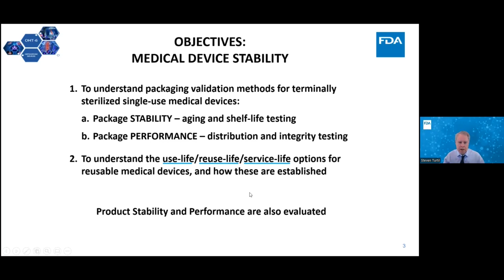So I'm going to introduce you to some terms, but the first and most important one for context is a sterile barrier system, and we often abbreviate this as the SBS. This is the minimum packaging that minimizes the risk of ingress of microorganisms and allows aseptic presentation of the sterile contents at the point of use. And from a microbiological perspective, the sterile barrier system should be designed to assure adequate sterilant penetration. That's going to vary depending upon the sterilant, as well as maintenance of sterility, from the point of sterilization and manufacture to the time and place of the medical device use. Again, I'm emphasizing these 2 subcategories.